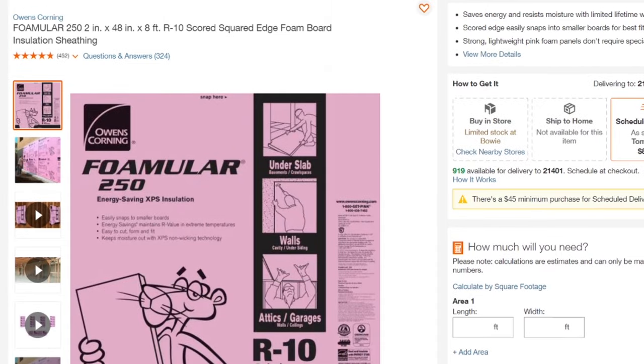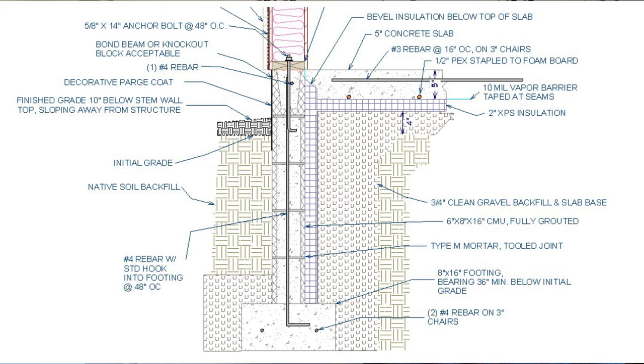Now that you know our reasons why we chose radiant heat, let's talk about how we're actually going to implement it. The first thing you need to think about, especially when you're doing radiant heat in a slab, is how not to lose all that heat into the ground. For us, that means two inches of extruded polystyrene (XPS)—the purple or green foam board you'd see at Home Depot. We're going to lay that all across under the slab and down the walls of our stem wall.